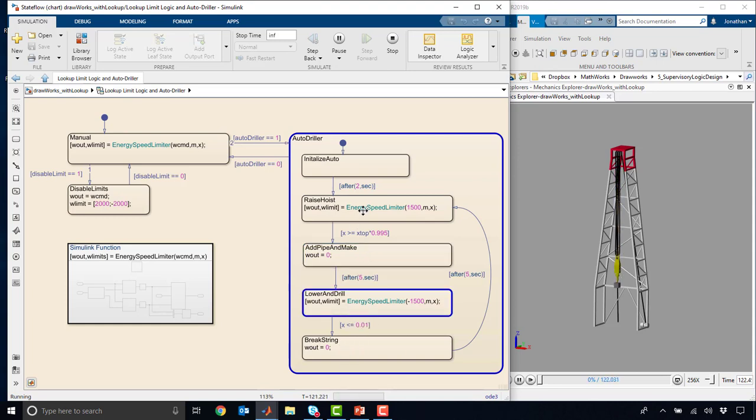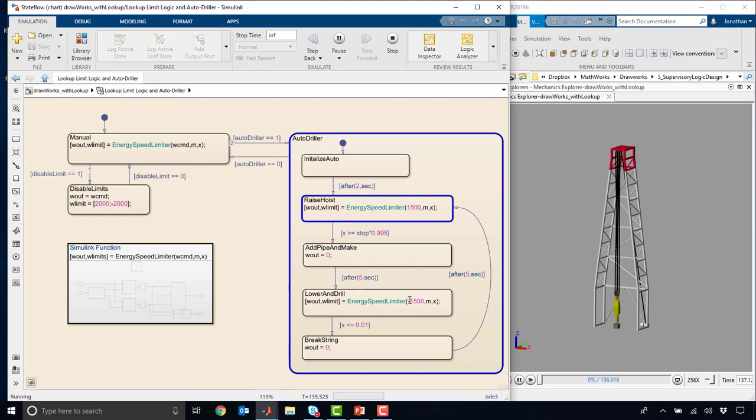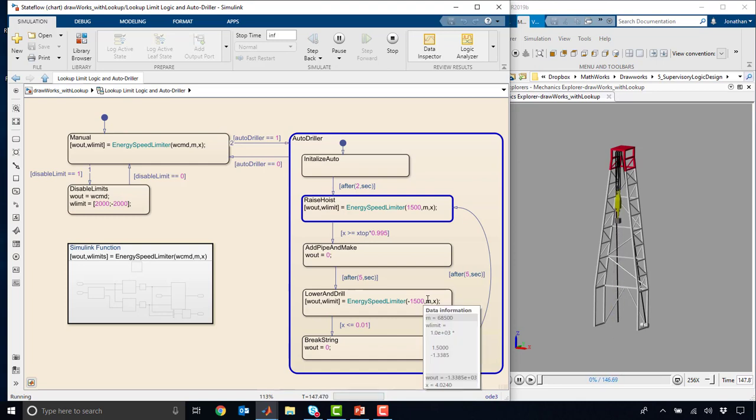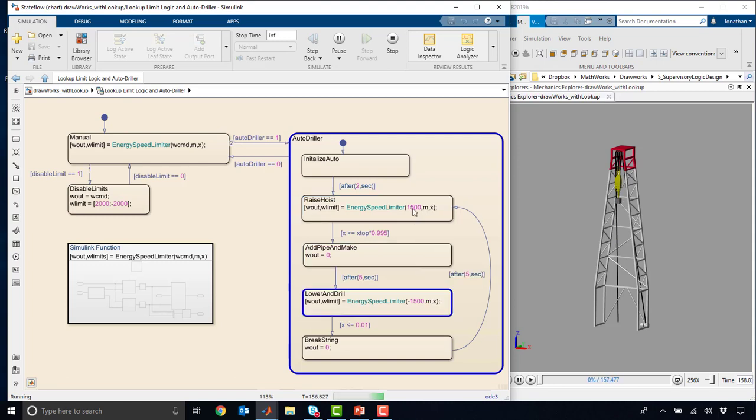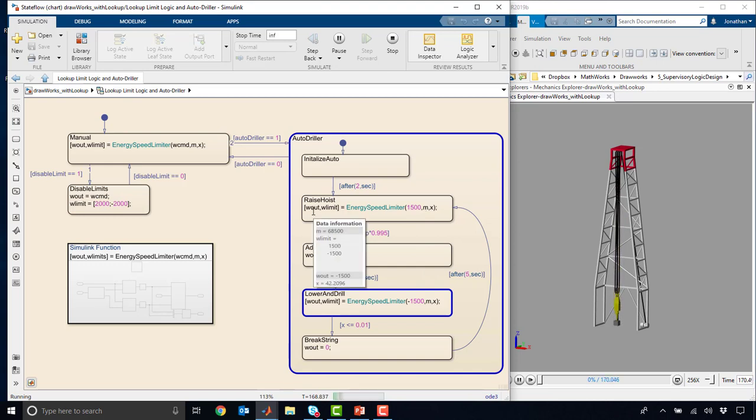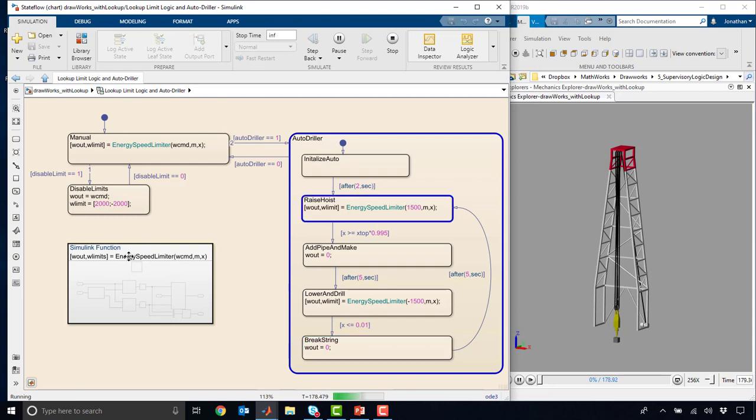You'll notice that in the raise and the lower states, we have this energy speed limiter, which basically takes in a speed command, in the lower case minus 1500 RPM, or in the top case 1500 RPM, and the current mass and the current position, and it will dictate what the actual limit can be. And this is coming from that lookup table that we built last time.